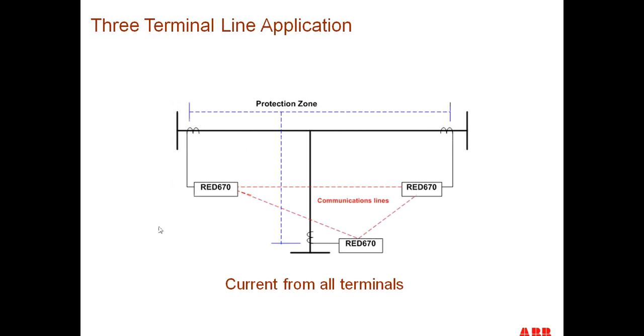So now let's talk a little bit about communication. There are various types of communications that you can use with this line. This is a typical example of a three-terminal line where we have this RED670, which happens to be the name of our line current differential relay. So we have three terminals of line current differential relays, and we have the communications between each of these. Each terminal is communicating to the other two terminals in a normal three-terminal line that you see here. And they all share the information together.